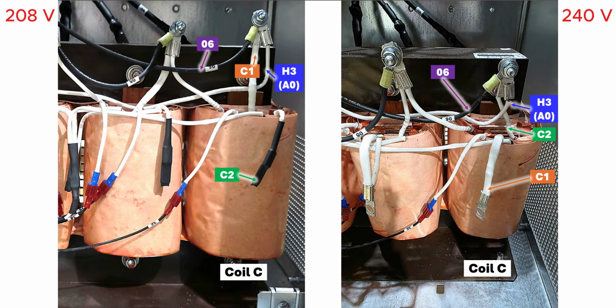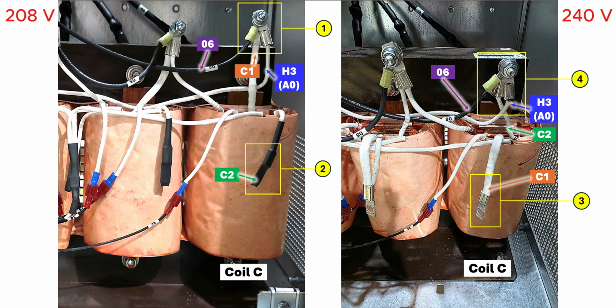We'll finish the process with coil C, swapping the wires that connect to H3. Number 1, remove the shrink wrap covering the H3 tap connections. Number 2, remove the shrink wrap covering wire C2. Number 3, keeping H3 connected to wire 06 from the AC circuit breaker, pull wire C1 out. Number 4, place wire C2 together with wires H3 and 06. Tighten the lugs for these wires together. Later, we'll shrink wrap the wires connected at H3 and separately shrink wrap the unused wire C1.